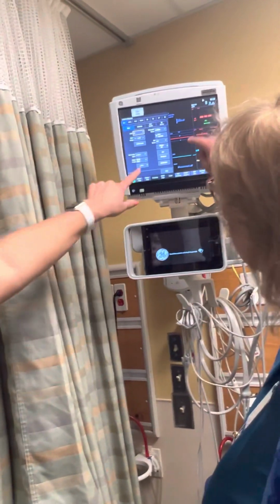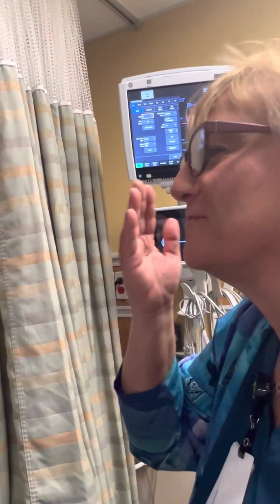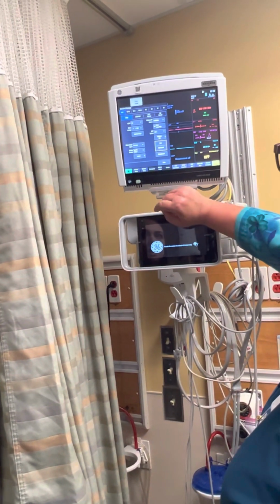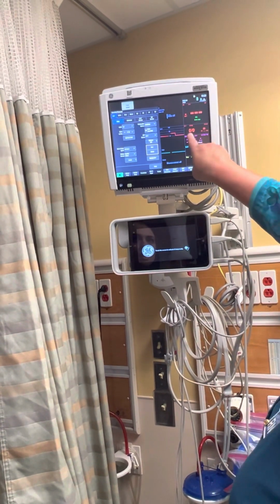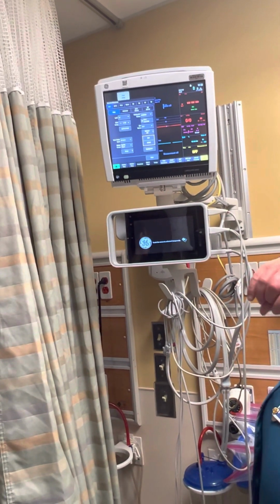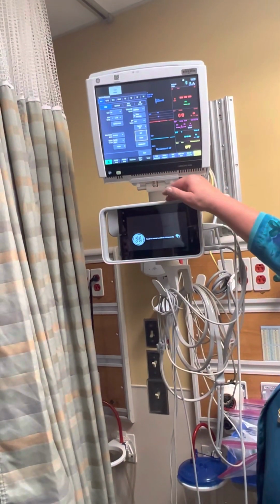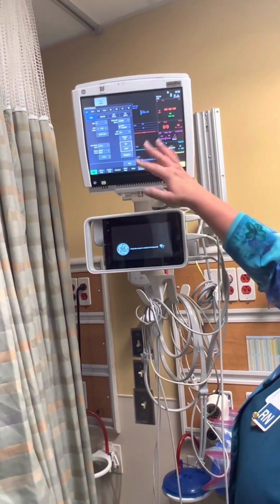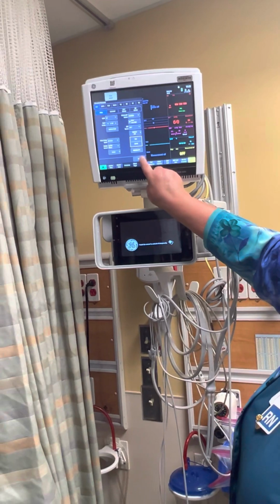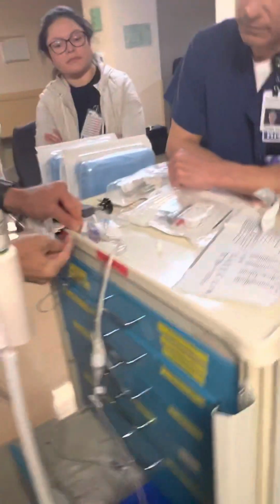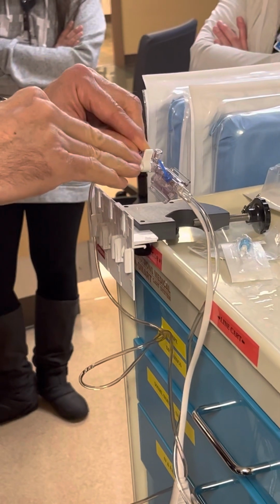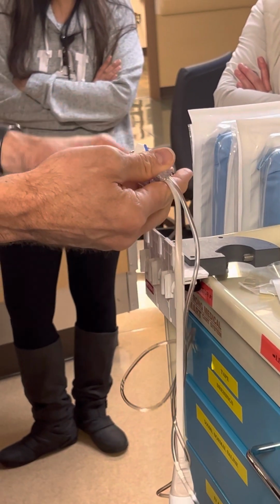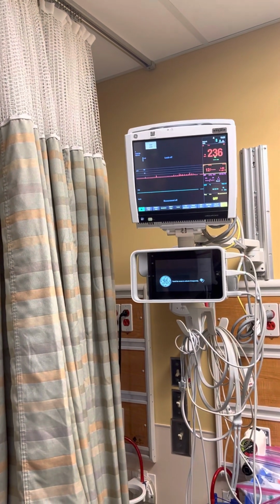Do you hit it and then zero? I haven't played with this. There's a zero right there. Oh, thanks. So tap zero. It'll do a zeroing, and see how it brought that line down to zero? It did a little step under, yeah. So then it's zero. Once that's done, you can turn this off so you get the pressure back from the patient, and then it'll start reading the pressure on this end. Oh. But again, aren't we going to have a cap on there? That blood pressure is measured, not on there? Yes.